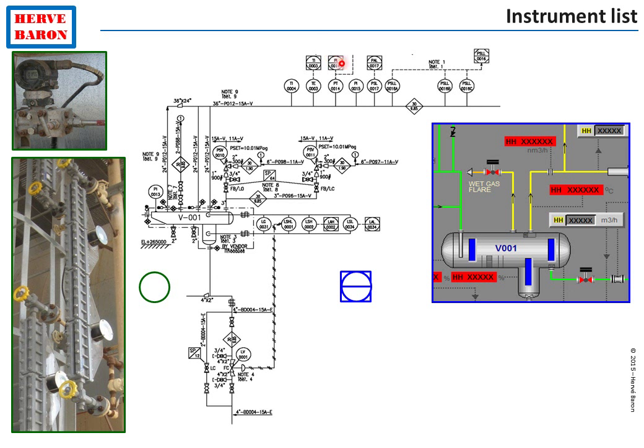For instance, this pressure indication is available on the screen of the control system, remotely from the control room, whereas this pressure indication is only available locally. This symbology is international — it is the International Society of Automation, ISA, symbology. So instruments with a circle are local instruments; instruments with a square frame are available on the operator display, remotely in the control room.